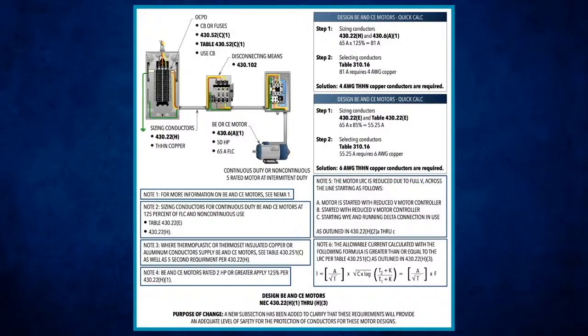I was on NEC Live for two weeks. The first week I did conductors, the next week I did overcurrent devices, and I made a statement. I said if you calculate anything at 125% or less, you go up to the next standard size overcurrent device. Anything above that percentage, you're going to drop down.